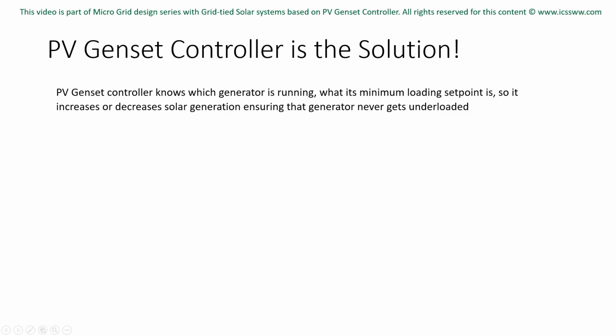The PV Genset controller knows which generator is running and what its minimum genset loading set point is, so it increases or decreases solar generation, always ensuring that the generator never gets underloaded.